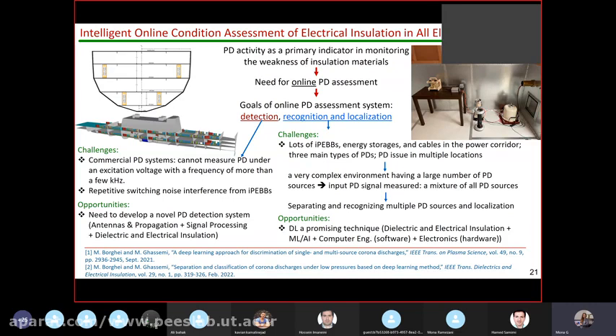We do the PD test as a routine factory test to ensure acceptable quality of our insulation system. However, over time, that initially accepted quality gradually deteriorates, because of partial discharges, electrical stresses, thermal stresses, mechanical stresses, and you can also add environmental impact. So we can consider PD as an indicator of the health of any insulation system.